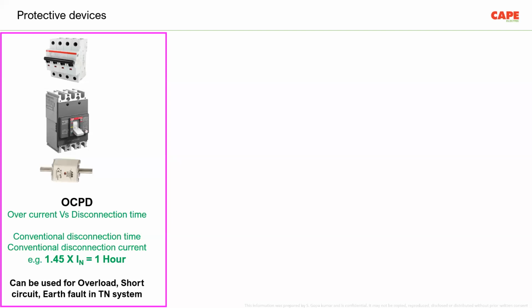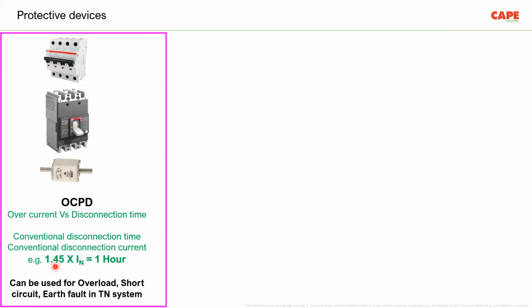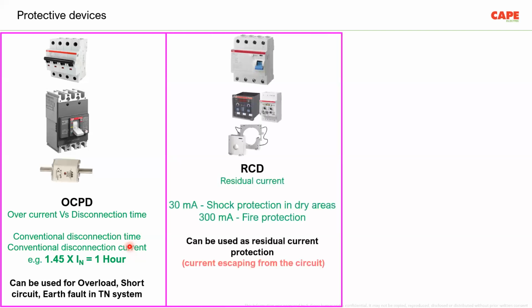Now in an OCPD, especially, let us say, for example, an MCB, there is a conventional disconnection time and conventional disconnection current, which is very much important. In a general situation, conventional disconnection current is about 1.45 times its rated current. And if the current is up to 1.45 times, an MCB can take up to 1 hour to trip. We should always keep this in mind. Of course, these protective devices are supposed to protect the cables of that particular circuit. It is also supposed to protect against earth fault in case of a TN system.